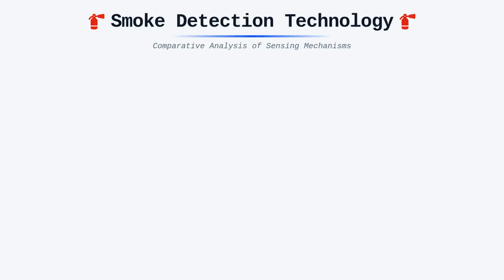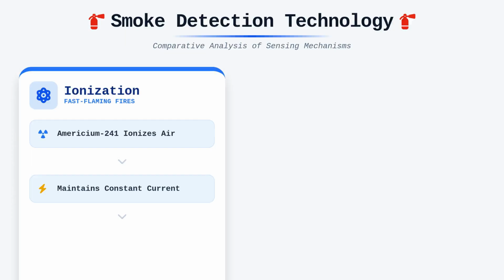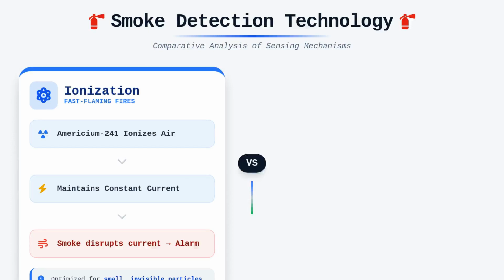To understand smoke detection, we must first look at the underlying physics of particulate sensing. Ionization detectors rely on a radioactive source, usually americium-241, to ionize the air within a sensing chamber, creating a small electrical current. When smoke particles enter this chamber, they attach to the ions, reducing the current and triggering an alarm. While effective for detecting smaller, invisible combustion products from fast-flaming fires, these devices have specific limitations concerning high airflow environments.